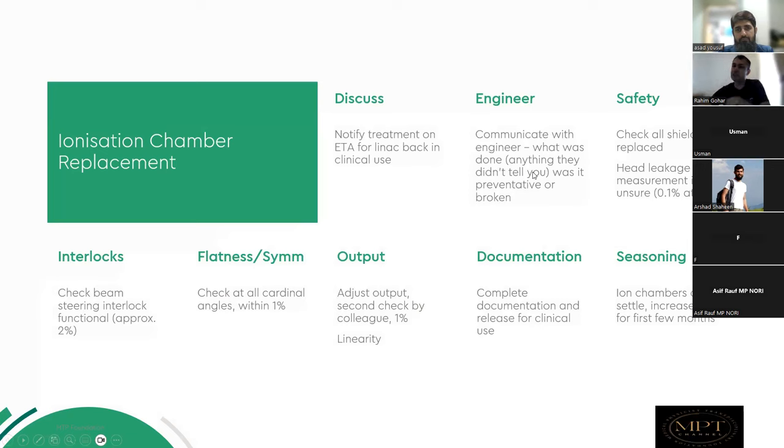Maybe he has changed something on the jaws as well, and the jaw calibration is out. Maybe the MLC needs recalibration. So, as you said, definitely you have to discuss. Right. And the timelines as well: if this is the running machine, then you will notify the administration that this is going to happen and it will take this much time to make it clinical.